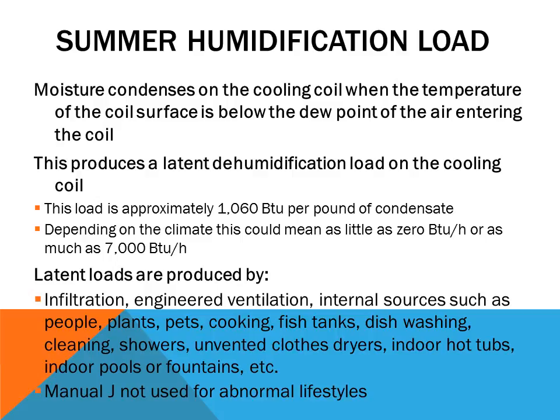In the summertime, we actually have to remove humidity, because when the humidity inside the building goes above 50%, you have a tendency to have mold and other bacteria grow and have issues. So latent loads we have to consider. People may have plants or animals or fish tanks, or let's say jacuzzis inside of the house, which add additional amounts of latent heat. And so we have to consider those and be able to determine that to help keep those levels at a safe level.